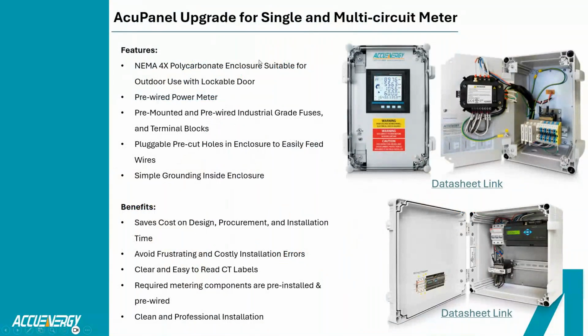A couple of units I think, and I've seen especially popular in the BAS industry, is our AccuPanel upgrades. Essentially what we do here is we take any of our meters, whether it be the AccuVim 2 or the multi-circuit meter, and we mount them in an IP66 NEMA 4X rated enclosure. We pre-wire the meter back to pre-labeled terminal blocks for your CT inputs and your voltage references. Your voltage references are going to have fuses in here, so it is protected. Essentially the purpose of this package is to speed up installation, eliminate any sort of installation errors with everything being pre-wired and pre-labeled, and just really save money on labor.